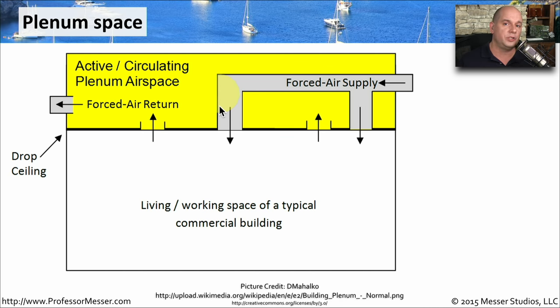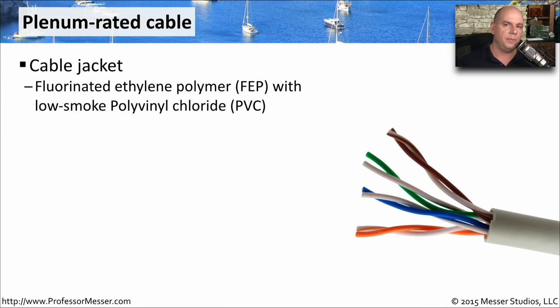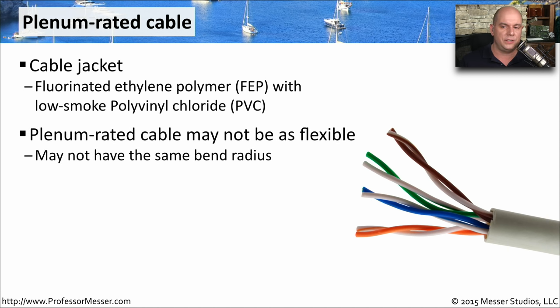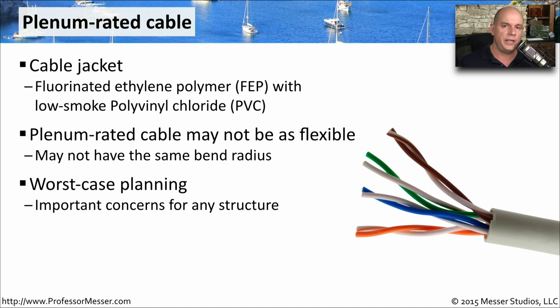If there is a fire, all of the smoke and chemicals from network cables in the plenum will get into the airspace, so we have to think carefully about what type of cables we use there. Fortunately, there's a type of twisted pair cabling designed for the plenum, using a fluorinated ethylene polymer with a low-smoke PVC jacket. This means that if there is a fire, it produces a minimal amount of smoke compared to other twisted pair cabling. This cable may not be as flexible or have the same bend radius, but you have to consider the worst-case scenario of a fire and making sure everyone can get out safely.